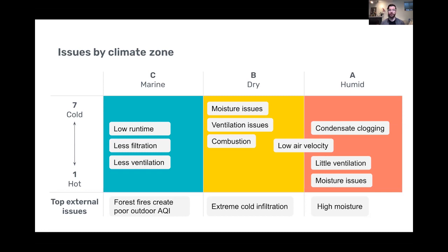You also see, depending on the air velocity going through the HVAC system, you may see that the coils of the air conditioner are going to freeze up. And this can happen because someone doesn't change their filter, and the extreme runtimes, because the environment is so different outside than inside. You have a lot of runtime that clogs up the filter. It clogs up the evaporator coil full of dirt. It clogs up the condensate drain full of gunk. And that results in all sorts of downstream issues where maintenance becomes more important. And maintenance is critical to indoor air quality.